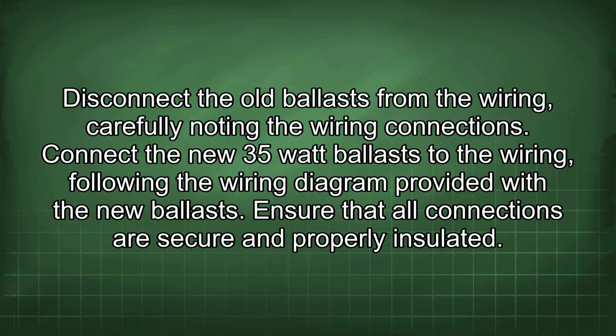Disconnect the old ballasts from the wiring, carefully noting the wiring connections. Connect the new 35-watt ballasts to the wiring, following the wiring diagram provided with the new ballasts. Ensure that all connections are secure and properly insulated.